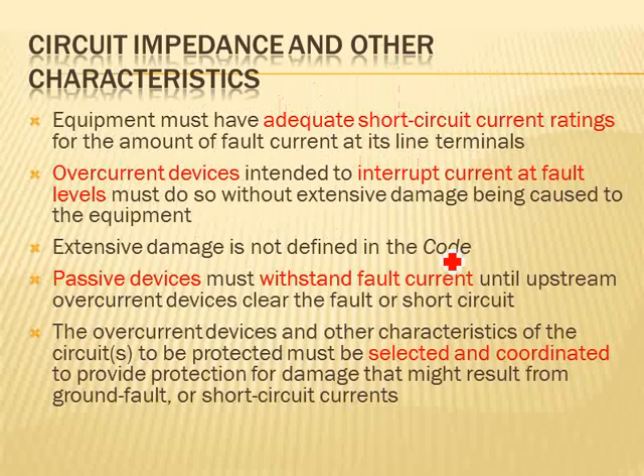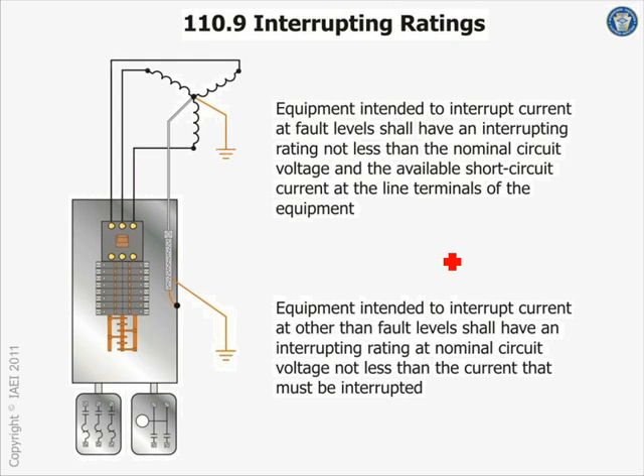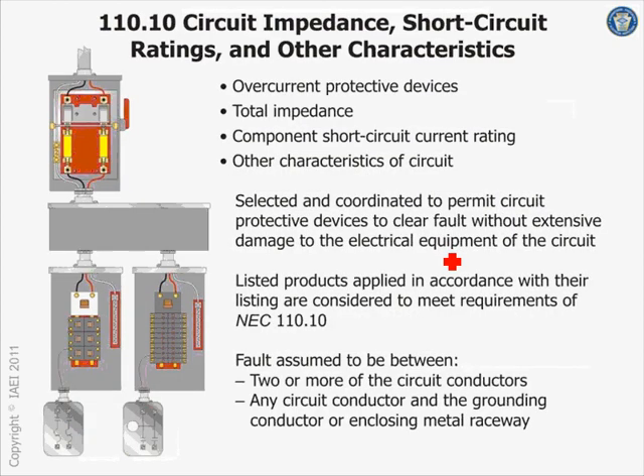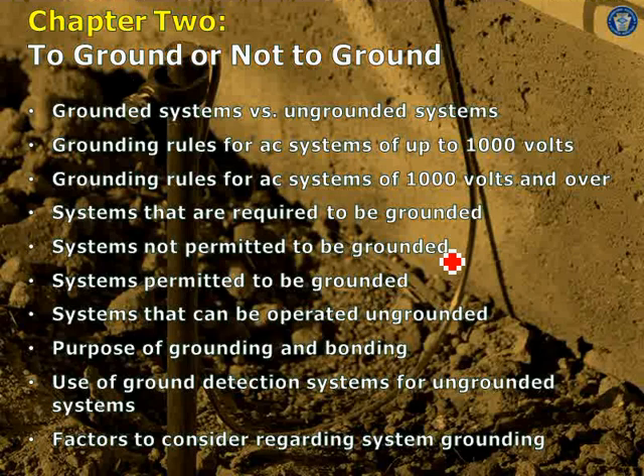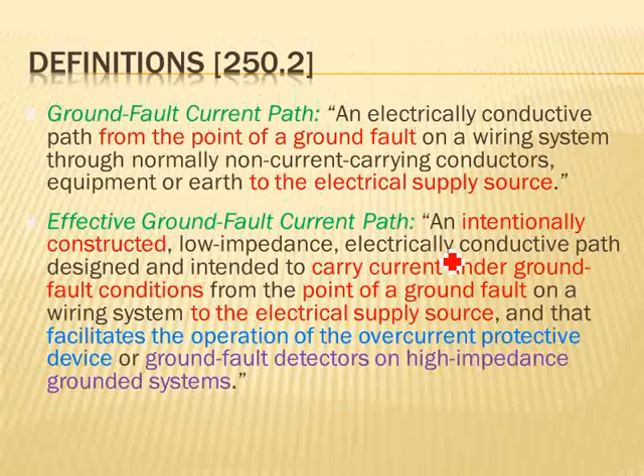Okay, short circuit. Let me see. Interrupting: this talks about the interrupting capability, guys, of the short circuit system. So the overcurrent device has to have the capability of interrupting the largest amount of current imposed on it. We'll talk about this in the second section. Circuit impedance, short circuit characteristics, we'll talk about these in the second segment. This is only chapter 1. So you guys will stay here for a long time to get into chapter 2.